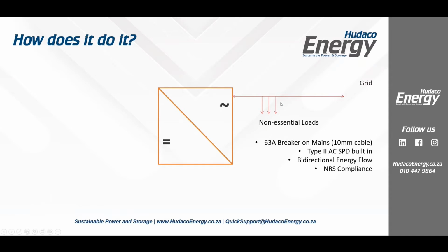Okay, over here, we're also going to put our non-essential loads. So we would put things like geysers, pool pumps, ovens, things which you don't want to run on battery power. Doesn't mean that you can't run them on battery power, but that you may not want to always run on battery power if your battery power is limited. Also, we have type 2 surge protection built in right here as well. This port allows for bi-directional energy flow. It is not a one-way port. It actually allows energy to flow from our inverter out into our loads here, as well as from grid into our loads and from grid into our inverter.